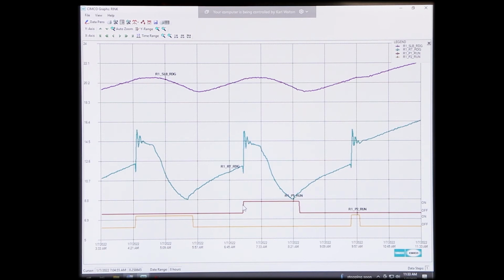The ideal thing you want to try to do here, still have good ice, but increase your off time. Now, that's what happened when I kept the ice at 20 degrees. Night, setback, and day. Okay. Now, when you go to a higher night setback, as long as the rink is nice and cold, all the doors are shut. How many rinks I walk into, they leave the Zamboni doors open at night. Keep the cold in the bowl, okay? I should have it with a smiley face on a t-shirt. I should have that. You do that, the package runs so much less. It really does. It keeps that cold within the dashers, and you run far, far less.